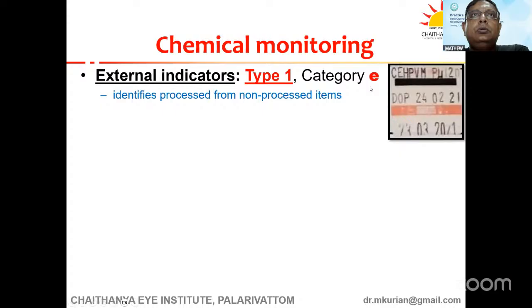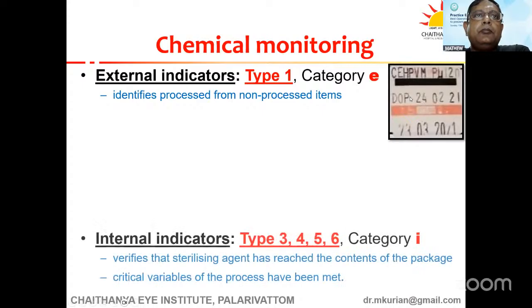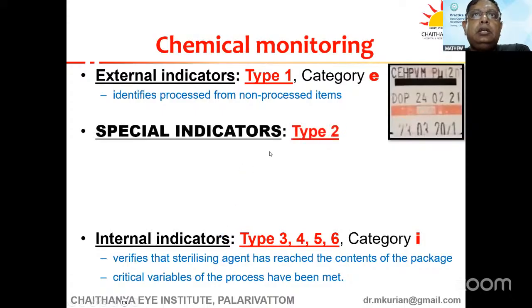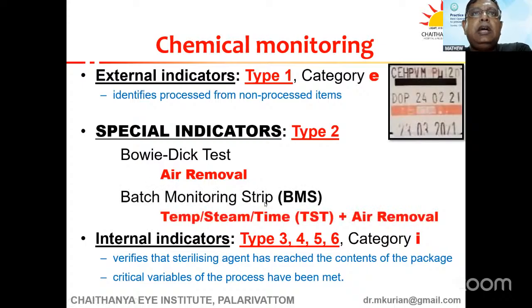And what we do is validated further by chemical monitoring. External indicators or type 1 indicators or category E indicators are something like this, which is just to say that a process has happened. Internal indicators are type 3, 4, 5, and 6, and these are called category I indicators, and they verify that the sterilizing agent has reached the contents of the package. So this should be inside the pack or set that you're using. But more importantly are special indicators or the type 2 indicators. This includes the Bowie-Dick test, which confirms that air removal has happened, and batch monitoring strips, which inform that the temperature, steam, and time, TST, and the air removal have been completed.